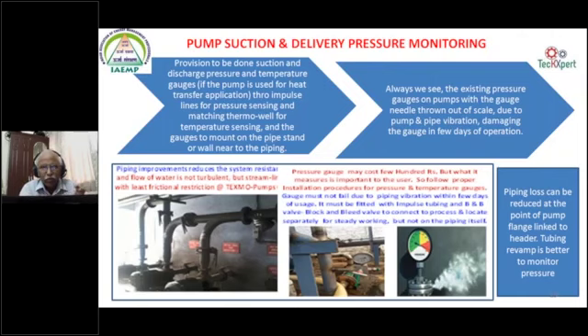And the block and bleed valves that are fitted on the pressure gauges need to be monitored, so that you can see across the line the pressure gauge is also working. At the same time we can check the zero of the gauge, and monitor the range of the process that is there. The impulse line can also be brought to a stand next to the pipe and fixed, so that the pipeline vibration need not transfer to the gauge. Otherwise, within 2 days or 1 week after the pressure gauge installation on the pumping line, the gauge needle comes out and doesn't show anything. So you also have the comfort of monitoring the gauge, or fixing the gauge in a robust installation.